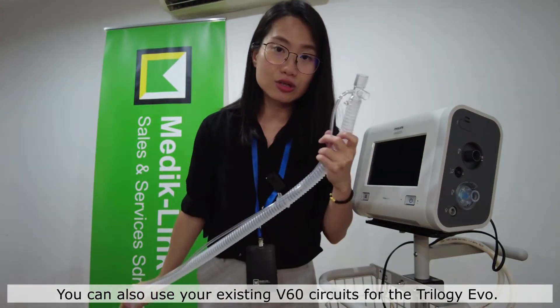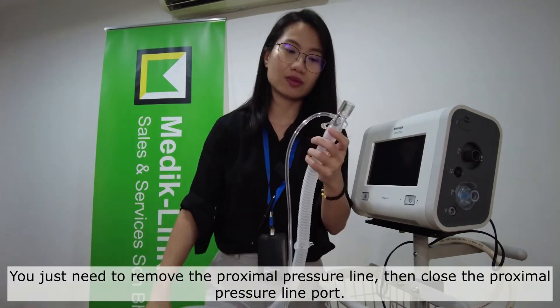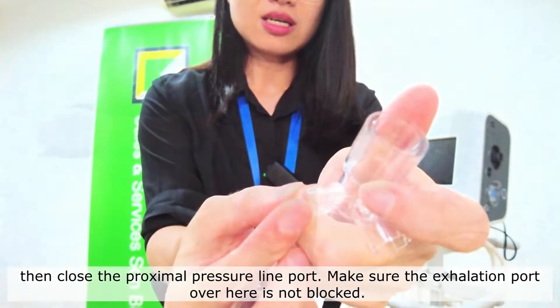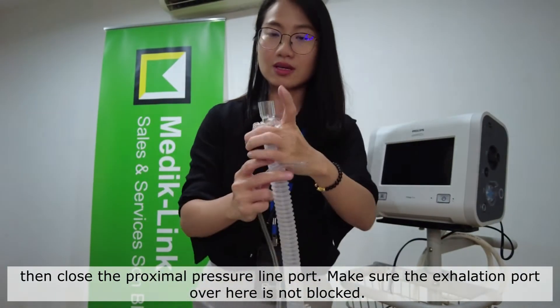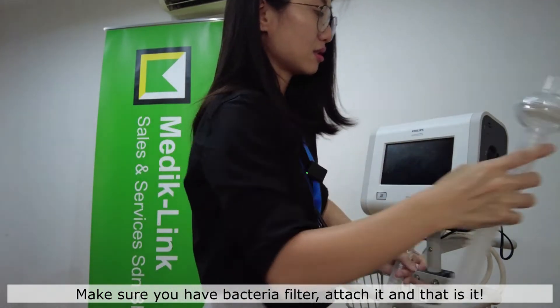You can also use your existing V60 circuit for the Trilogy EV300. You just need to remove the proximal pressure line and close the proximal pressure line port. Make sure that your exhalation port is not blocked and that you have a bacteria filter.